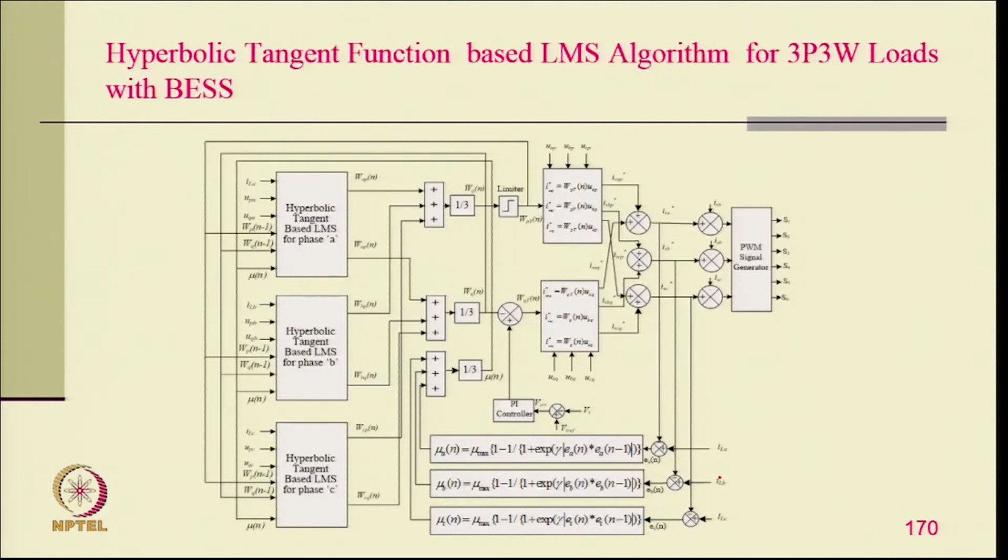Then we have a hyperbolic tangent function for the battery energy storage system, where we again extract the fundamental component for all three phases, typically called the active component, and similarly for the reactive component. Terminal voltage regulation is required on the AC side, but for this we can limit it, because we are putting in the battery.